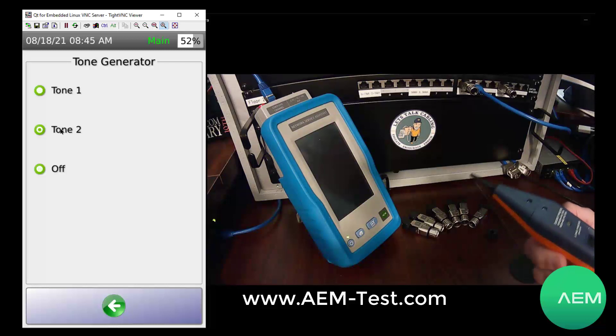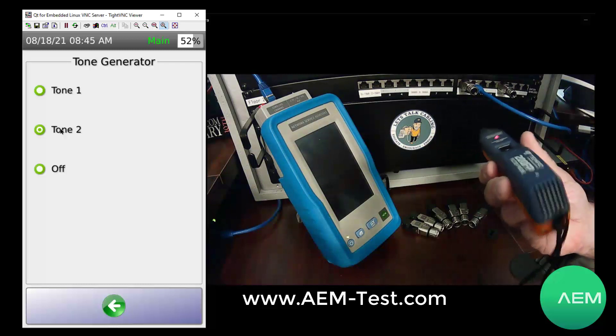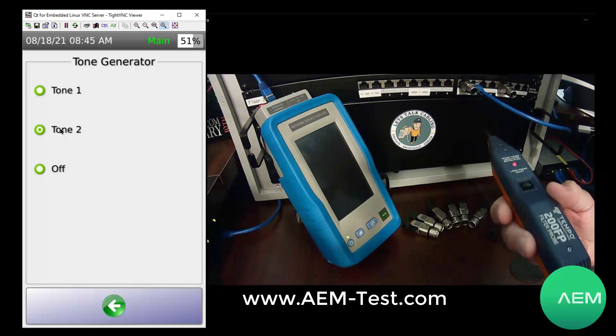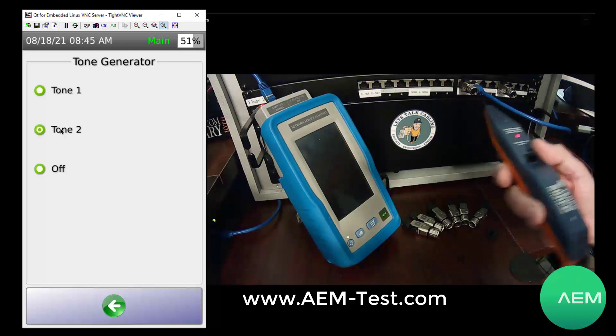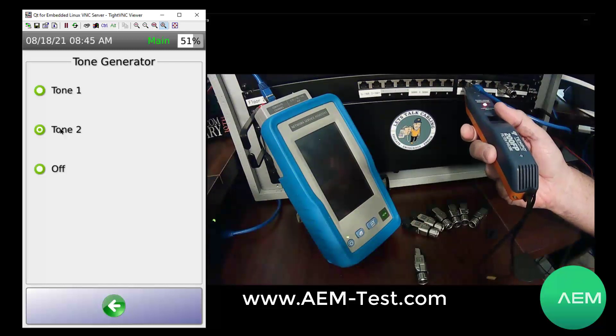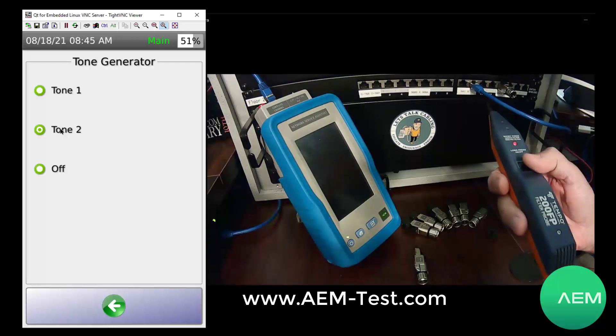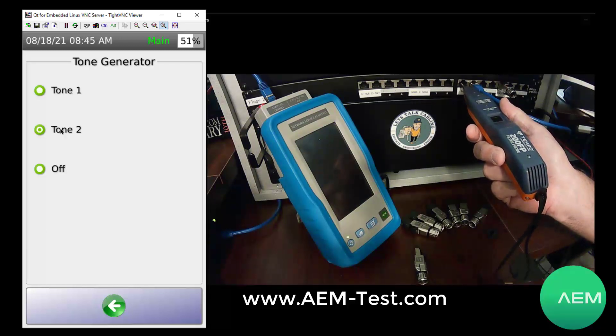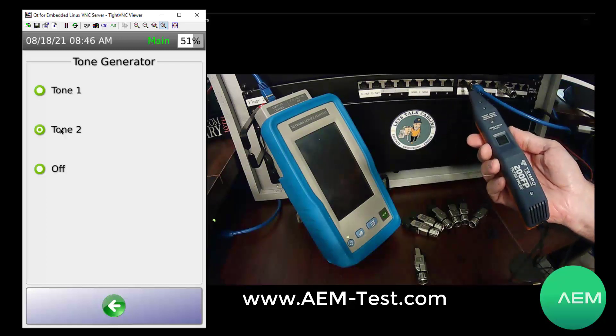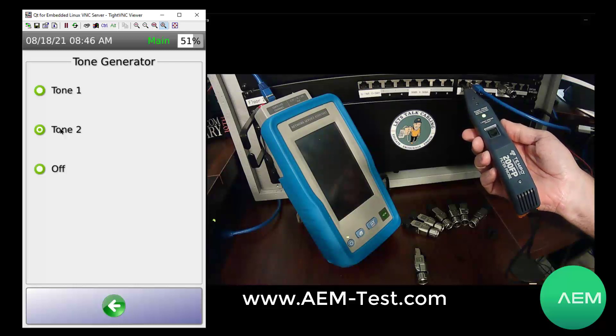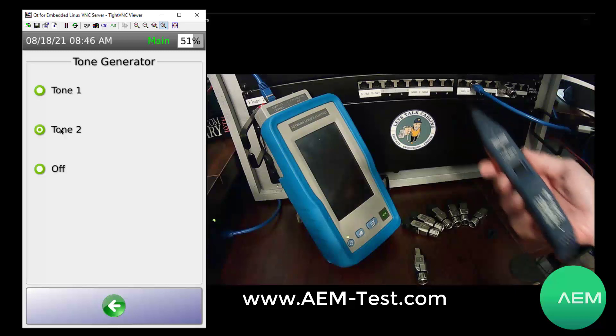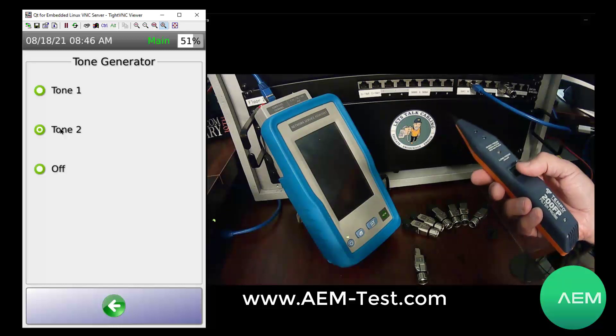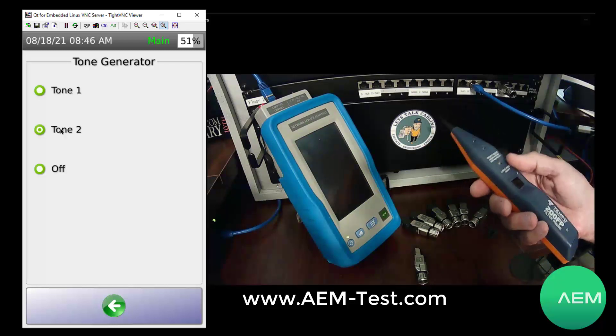I'll select tone number two and turn the probe on. When I first turn it on, you can hear a buzz from AC voltage harmonics — that's very common. Anyone who has done tone and probe operation has seen this; it doesn't matter what kind of RF probe you're using, you're going to see this buzz. Sometimes you can still find that tone and get to that jack, but sometimes you may not be able to pick up the tone. I'll hit the filter, and now I can find that tone much more readily. Additionally, there is an LED on the probe that blinks and gets close to solid as we get right on that wire — it's a signal strength indicator. If you're in an environment with a lot of equipment and background noise and can't really hear the tone, you can watch that light and know you're on the tone.